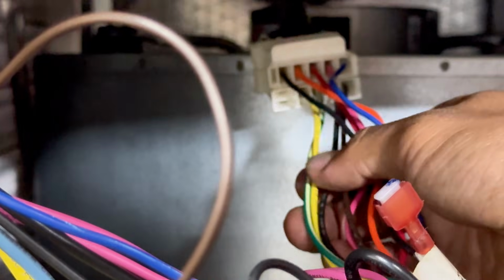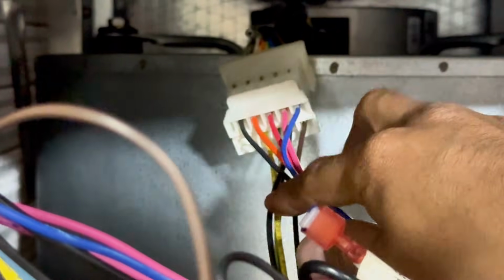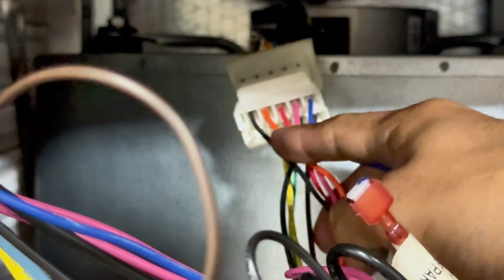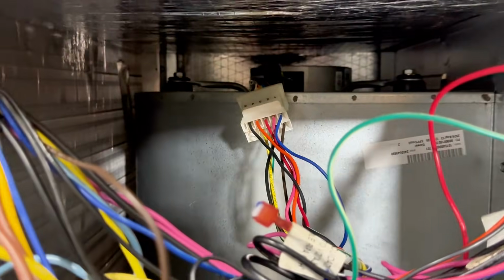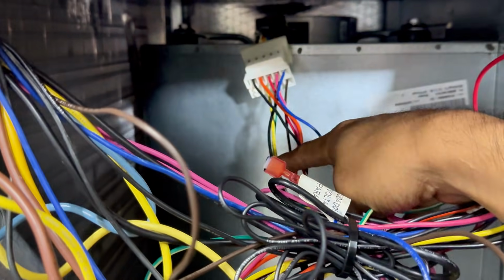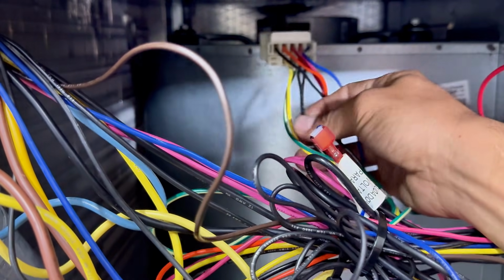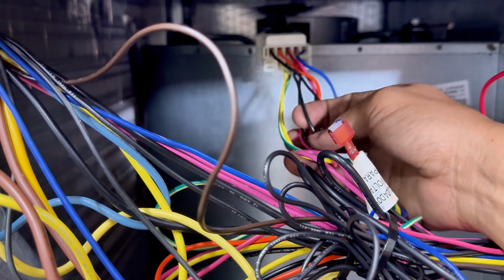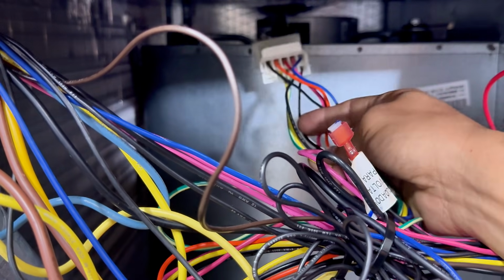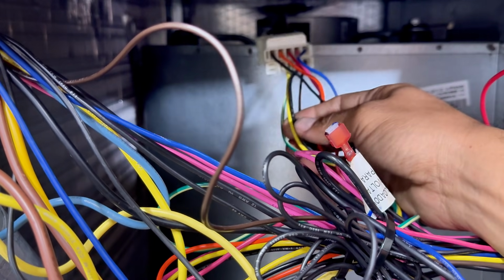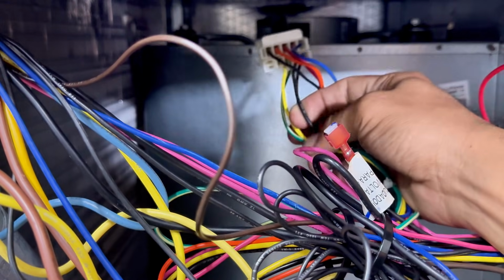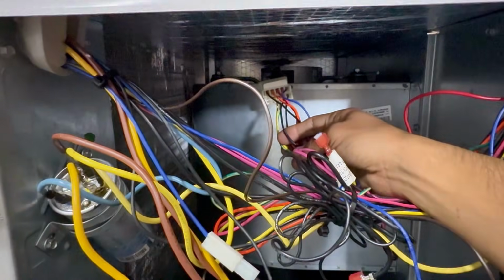So right now my ECM motor has 208 volts present. But what actually gets the motor to turn on is when one of the speed taps receives 24 volts. So what I'm gonna do, like I had mentioned earlier, you usually check it on the common, which tends to be black. And the ECM motor example though, with this one, it doesn't really matter because of the way it's wired, but we'll just take it black, put it on the black just to keep it simple.